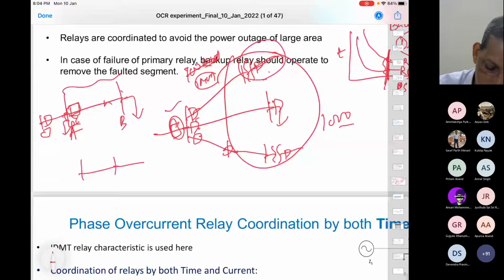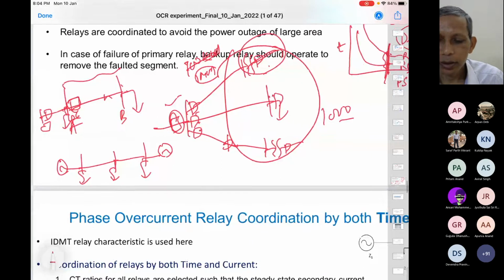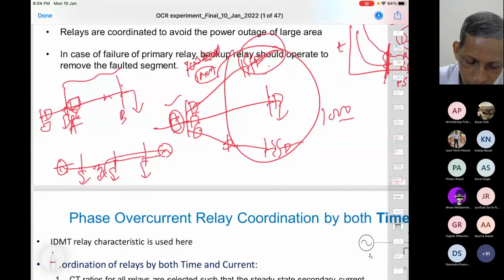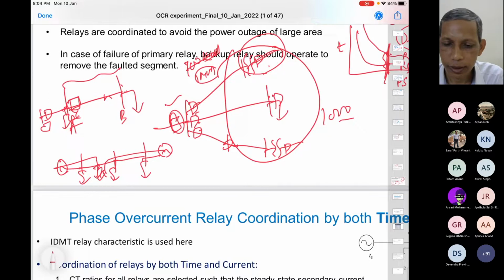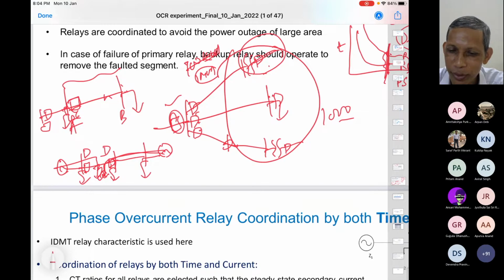Right? Like you see here, system here. When you go to the high voltage system, I have interconnection like this. Current is fed from this. Our 400 kV network in the power system is a loop system. Our 765 is a loop system. All are interconnected, sources are from both ends. So a fault happens to be here. Current flows from this side and current also flows from this side. Agree? Now in this case, if you require one and only breaker, still this fault will continue to be fed from this side. So you require a breaker at both the ends, here also, here also. Breaker means relay also. Agree? A breaker cannot operate normally by itself. Is it okay now?